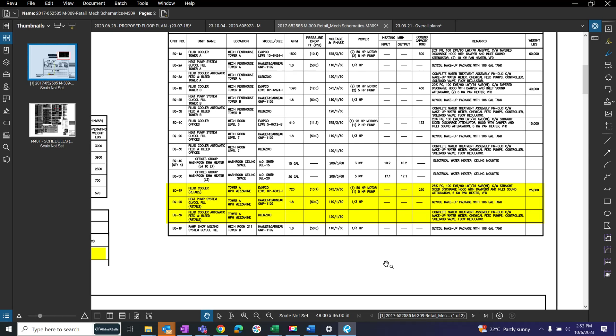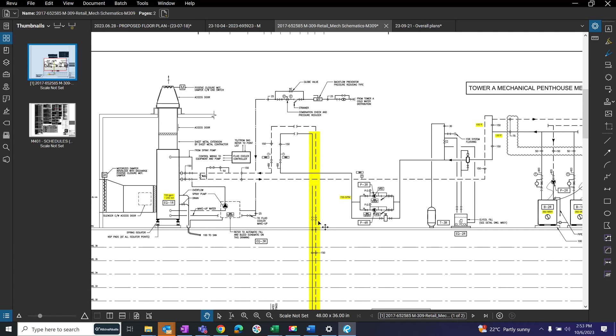Normally that's the case, right? You have a tower that dumps the heat, and then we heat pump out of whatever we get back, 90 degrees or whatever. But if you've got an actual compressing chilling plant of some sort, these values suggest it's not actually operating. So I think those numbers are wrong - I think it is bringing it down, because otherwise it has no purpose.